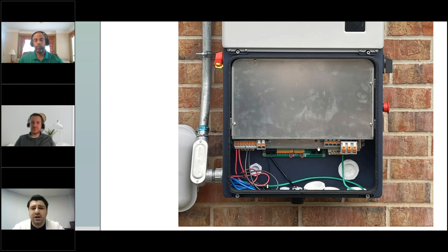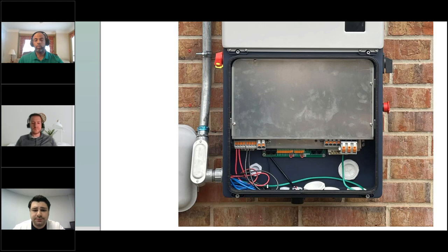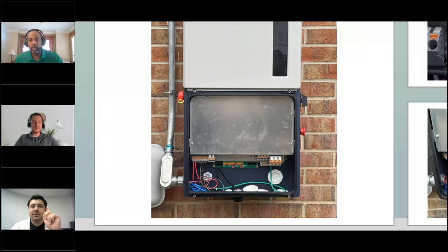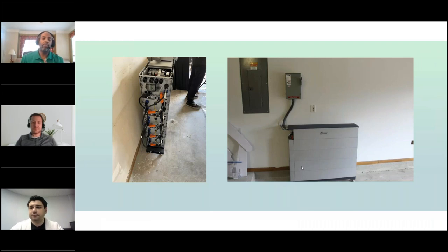These two port groups connect to the smart energy panel in terms of power. The three on the right side go to the smaller breakers at the bottom of the smart energy panel. The four on the left are the load ports — L1 and L2 go through that breaker on the main bus bar of the smart energy panel. Between the communications board and the MPPTs, there's one port for battery positive and battery negative. This is the battery being put together in series.